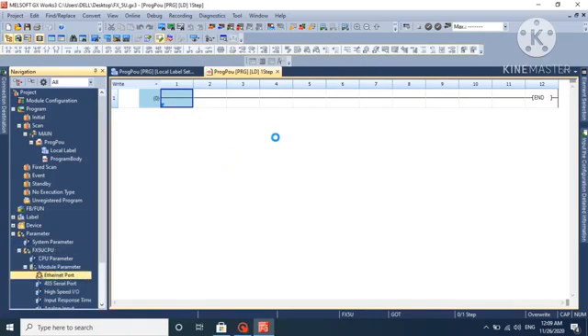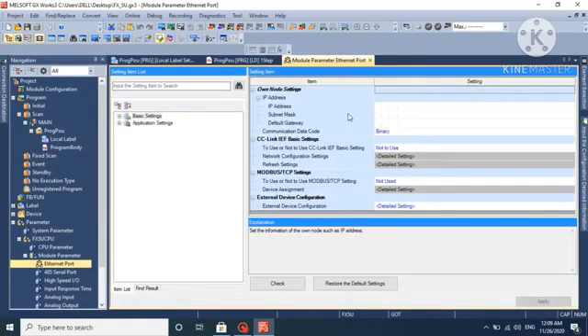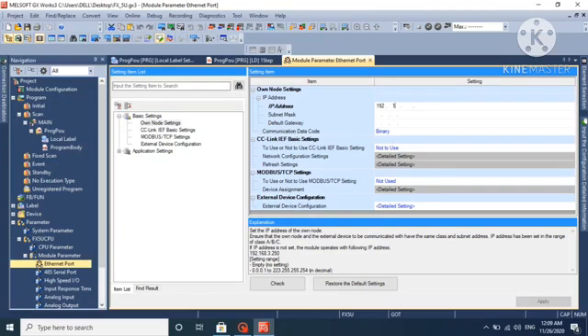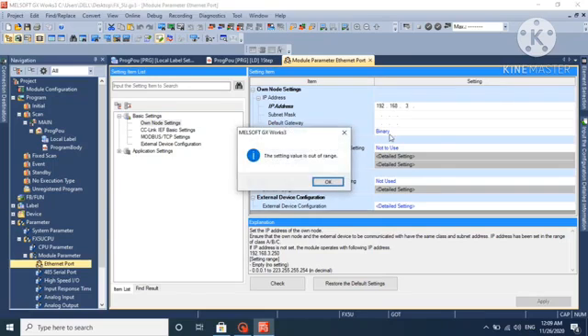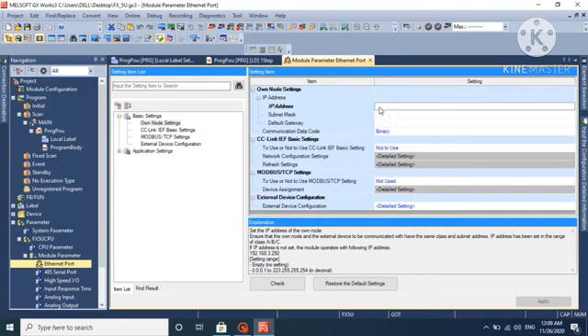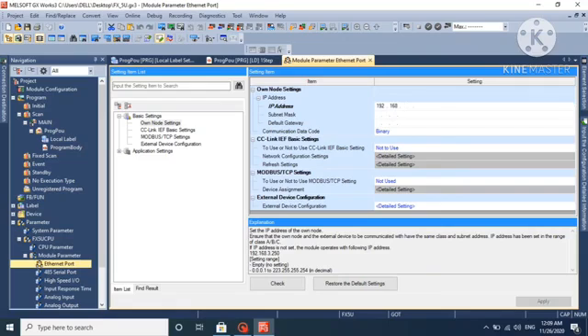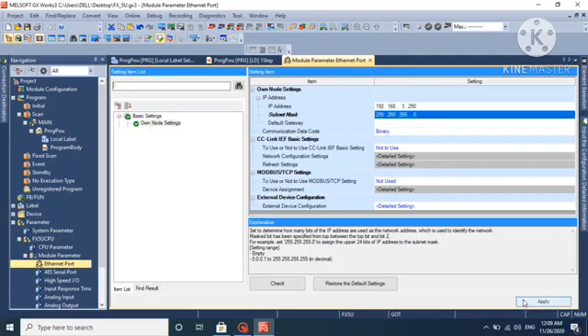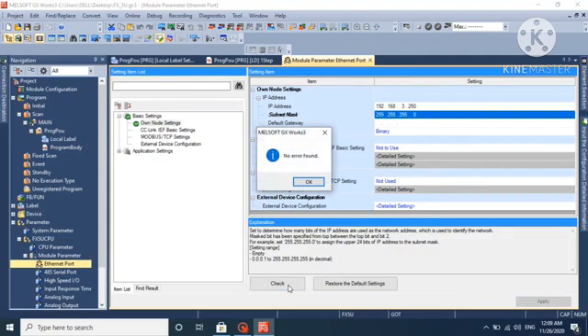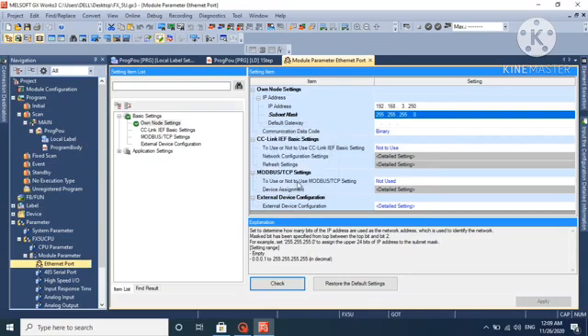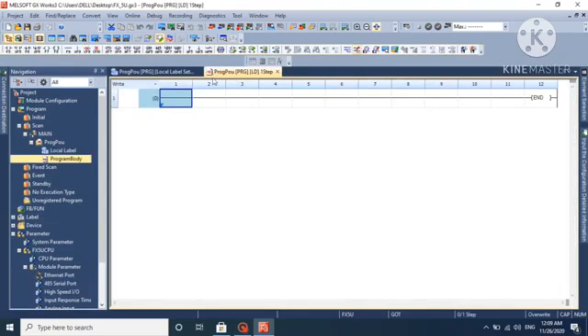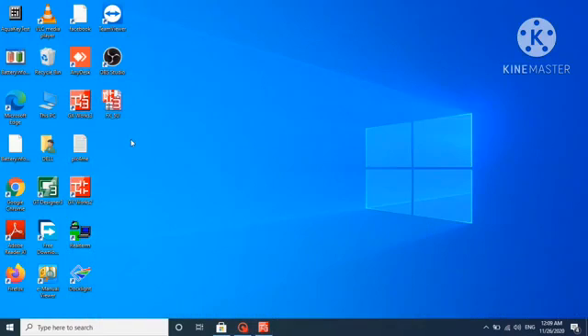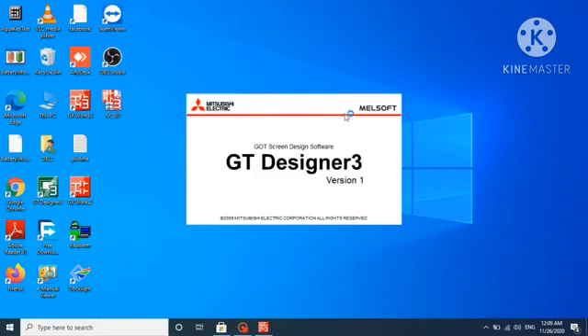In the FX 5U, we first need to assign an IP address. The default IP address of FX 5U is 192.168.3.250, so we will assign it here with subnet mask 255.255.255.0. Now we will apply the settings and check for errors. No error found.